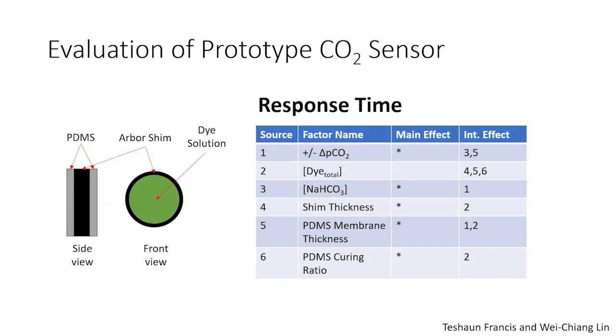We also spent quite a bit of time to understand the response time of the sensor. A Severinghaus CO2 sensor tends to be slow. Slow, I mean minutes or hours. But that's not good for physiological or biomedical applications. We need to speed that up. So we designed and carried out a factorial experiment to understand how sensor parameters, thickness of the membrane, concentration of sensor medium, and so on, interact with each other and how they impact the response time.